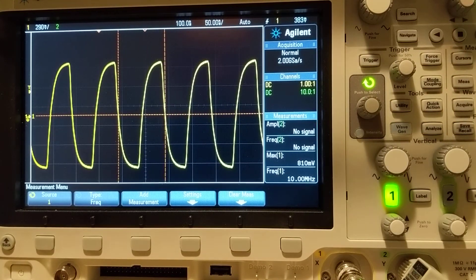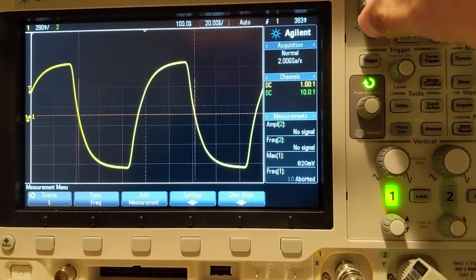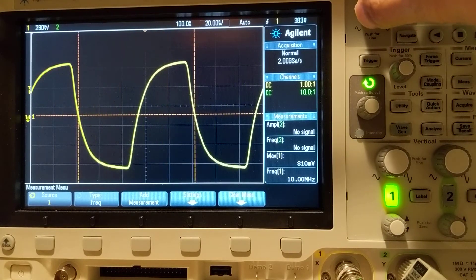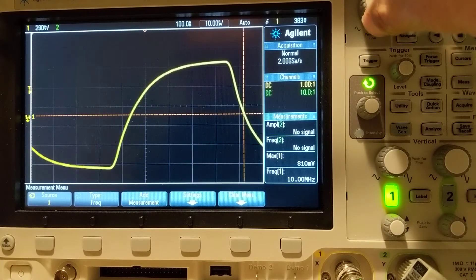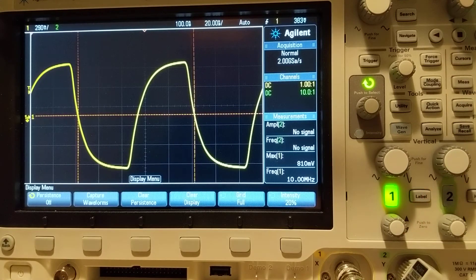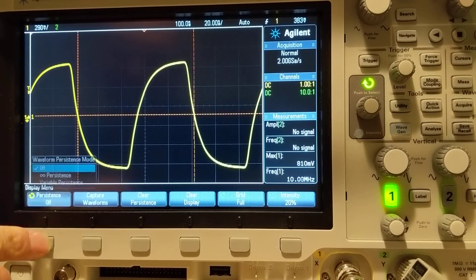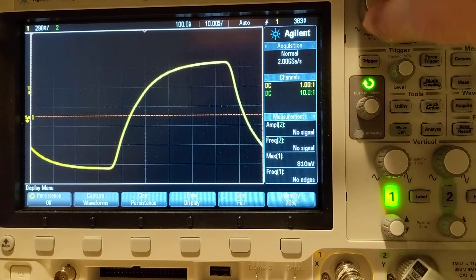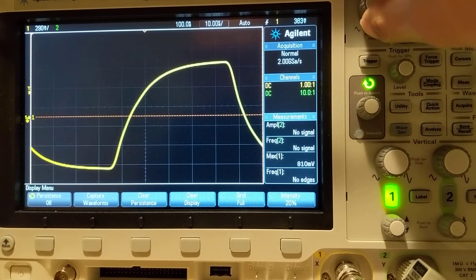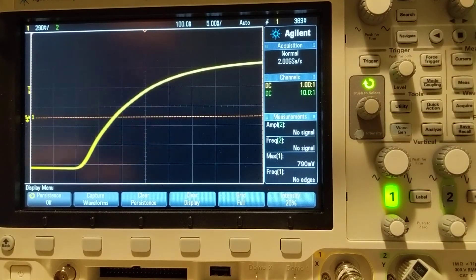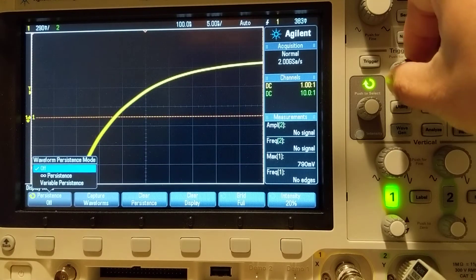Then I will set the persistence mode. The scope does not remember the previous scan, so we need it to remember the previous scan. Let's go to the persistence settings — right now there's no persistence, so the scope cannot remember the previous one. Let's go to the max and set persistence to infinity.